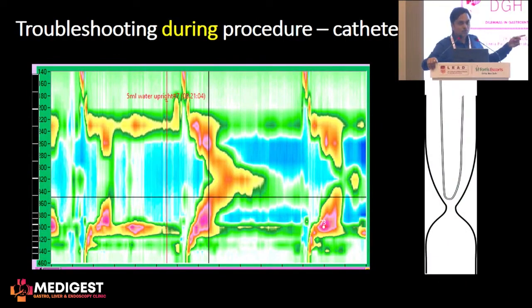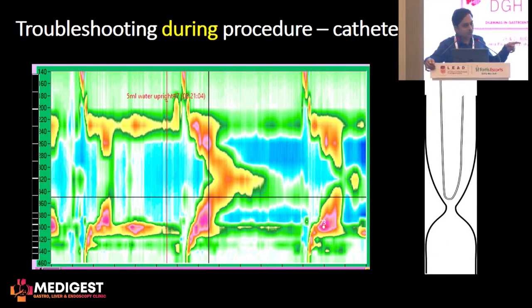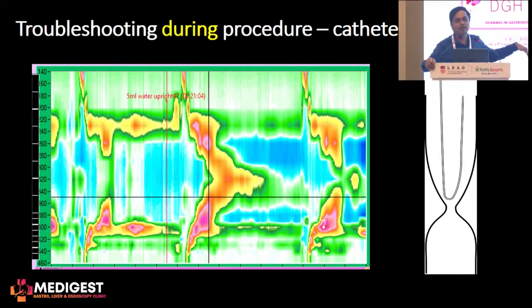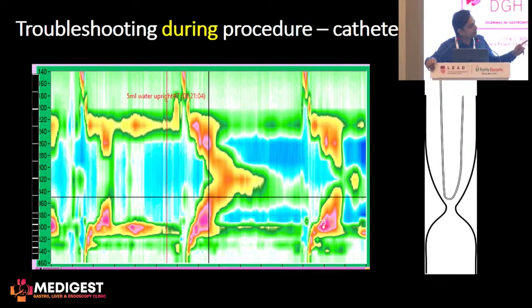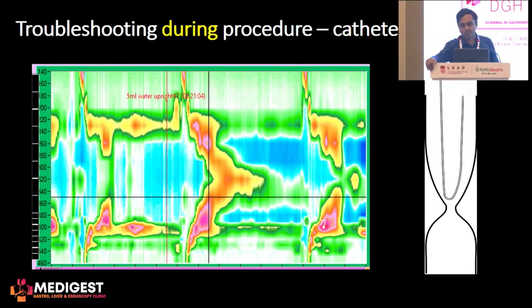Sometimes you can get a batwing kind of appearance, where you see peristalsis moving forward and then coming back — which never happens with true peristalsis. The problem here is that the catheter is kinked inside the esophagus, giving you a false batwing appearance in the pressure graphs.